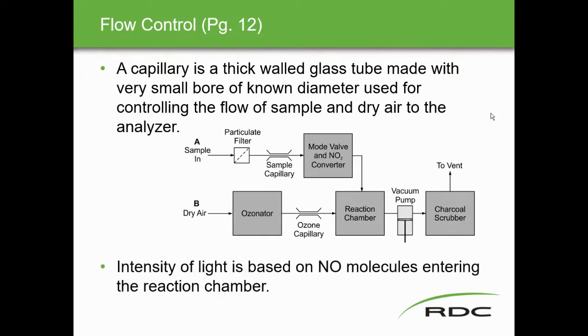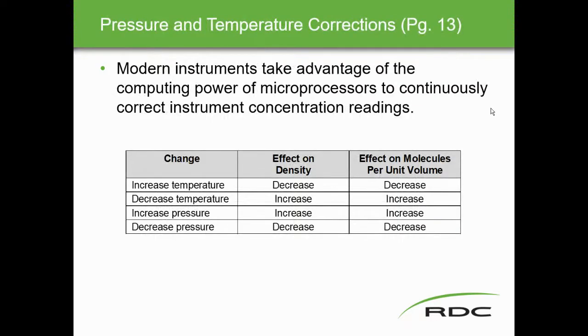The intensity of light is based on the number of NO molecules entering the reaction chamber. Modern instruments use microprocessors to continuously correct for temperature and pressure. As temperature increases, gas density decreases and the number of molecules decreases, which affects measurement — this is why temperature and pressure data must be fed to the microprocessor for accurate results.